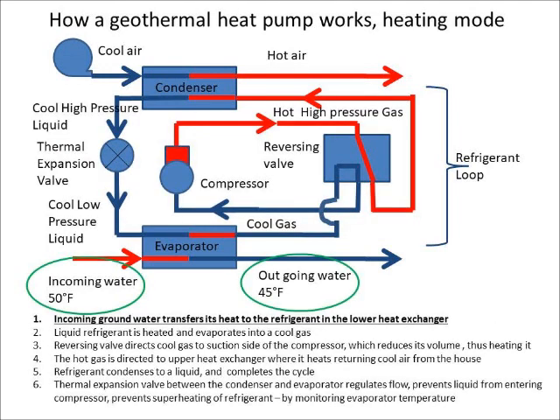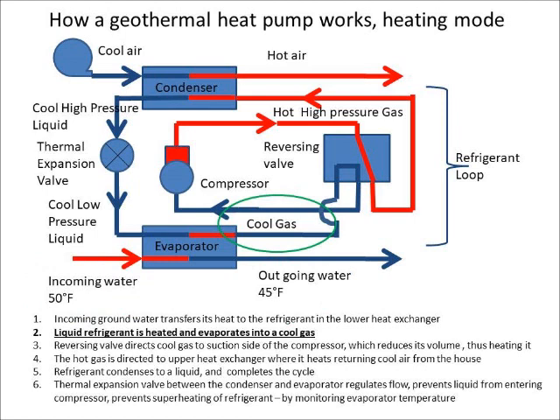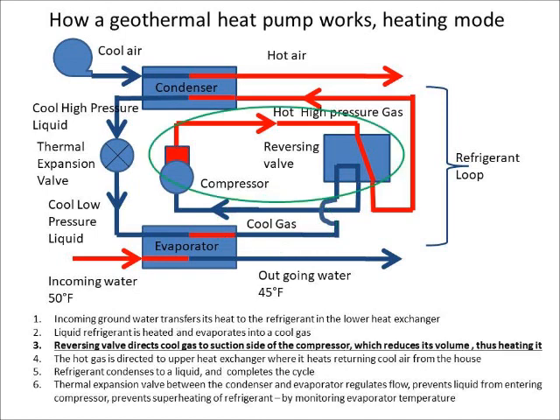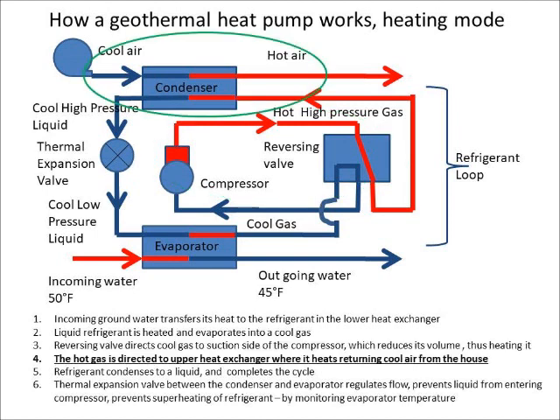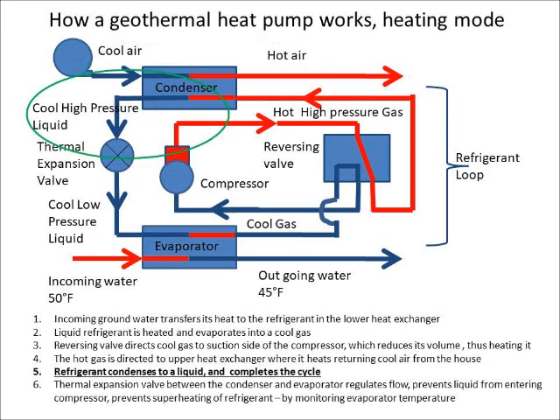This is a more detailed view of how the refrigerant transfers heat. First, the incoming groundwater transfers its heat to the refrigerant in the lower heat exchanger. Second, the liquid refrigerant is heated and evaporates into a cool gas. Third, the reversing valve directs the cool gas to the suction side of the compressor, which reduces its volume, thus heating it. Fourth, the hot gas is directed to the upper heat exchanger, where it heats returning cool air from the house. Fifth, the refrigerant condenses to a liquid and completes the cycle.